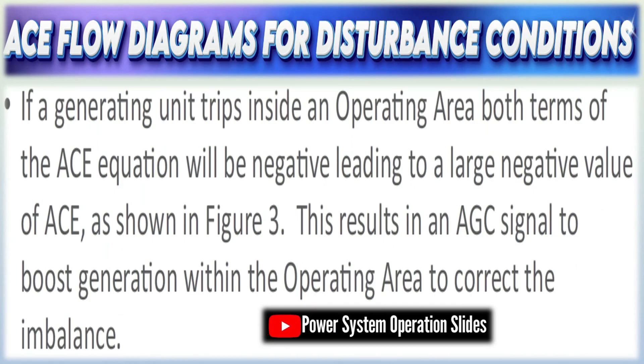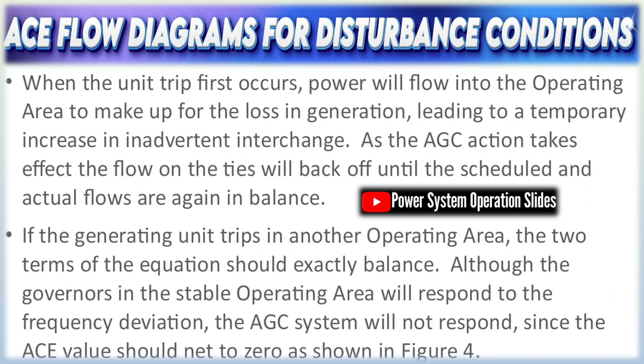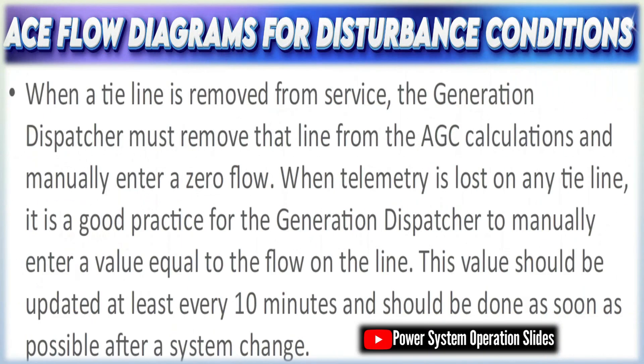Under disturbance conditions — such as a sudden loss of generation or an unexpected load surge — ACE flow diagrams help visualize the sequence of events and control responses. Step 1: A disturbance occurs, leading to an immediate frequency deviation. Step 2: Measurements of frequency and tie-line flows are fed into the AGC. Step 3: The ACE signal is computed as a combination of the power interchange error and the weighted frequency deviation. Step 4: The AGC controller processes this signal through feedback loops — often using PI (proportional-integral) control — to generate set-point adjustments. Step 5: These adjustments are sent to individual generating units. Step 6: The responding units modify their outputs over a defined ramp period, thereby reducing ACE towards zero and restoring nominal operation. Such flow diagrams are essential tools for operators in analyzing the transient response and verifying that the control strategy meets reliability criteria.